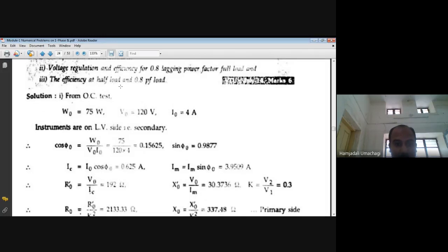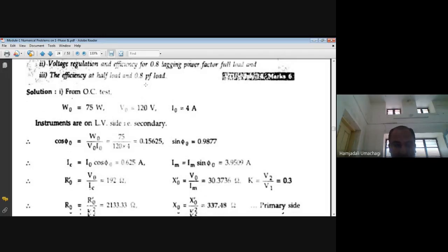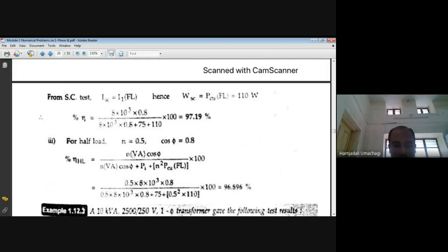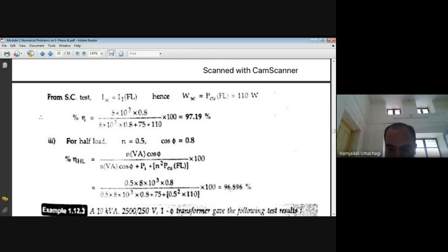Third parameter: efficiency at half load (n = 0.5) at 0.8 power factor. Percentage η = (n·VA·cos φ)/(n·VA·cos φ + W₀ + n²·PCu,FL) × 100 = (0.5×8000×0.8)/(0.5×8000×0.8 + 75 + 0.5²×110) × 100. Substituting values: efficiency at 50% loading at 0.8 power factor = 96.896%.